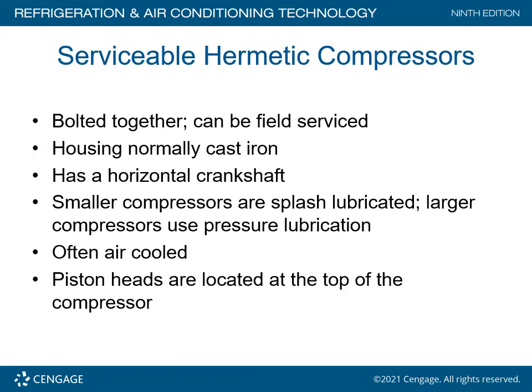Serviceable hermetic compressors are bolted together and can be field serviced. Housings are normally cast iron with a horizontal crankshaft. Smaller compressors are splash lubricated; larger compressors utilize pressure lubrication. They are often air cooled, and piston heads are located at the top of the compressor.